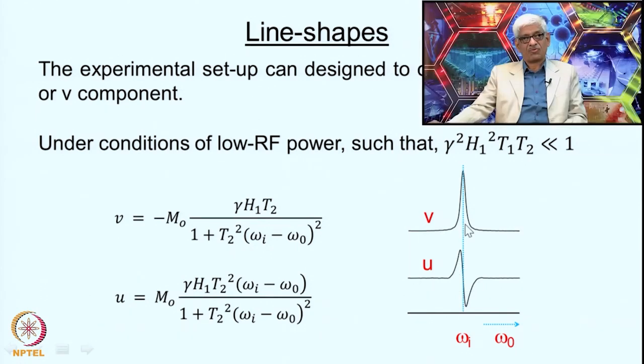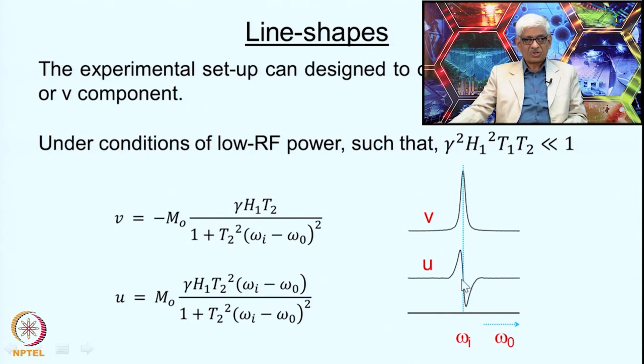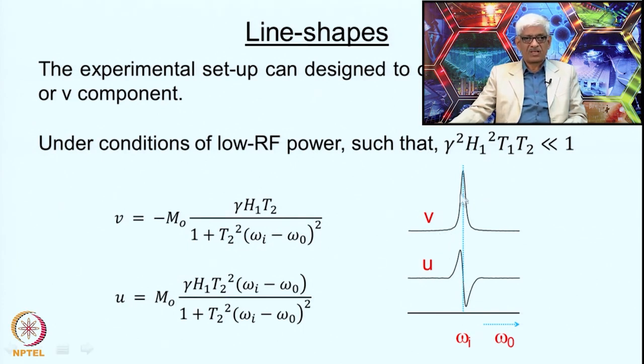Typically one uses the absorption line shape for drawing NMR spectra, but the dispersive line shape is also used for monitoring field drifts, especially for locking purposes. Dispersive line shapes are useful because it's easy to see deviation from the resonance condition — under resonance, this signal has the maximum and the dispersive signal is 0. The absorption line shape has a non-zero integral, whereas the integral of the dispersive line shape is 0.